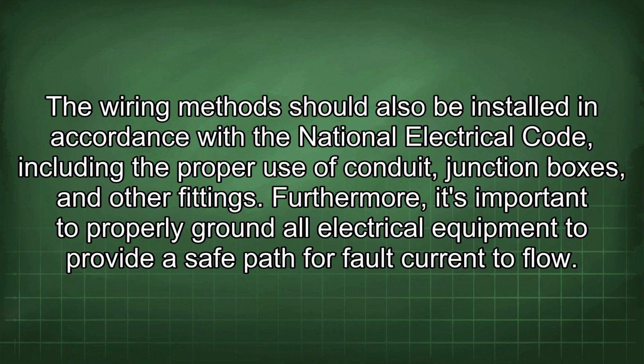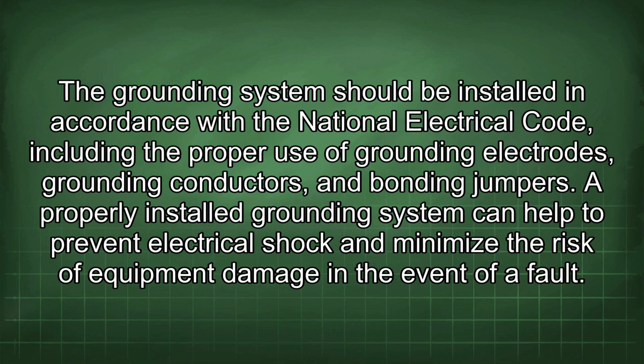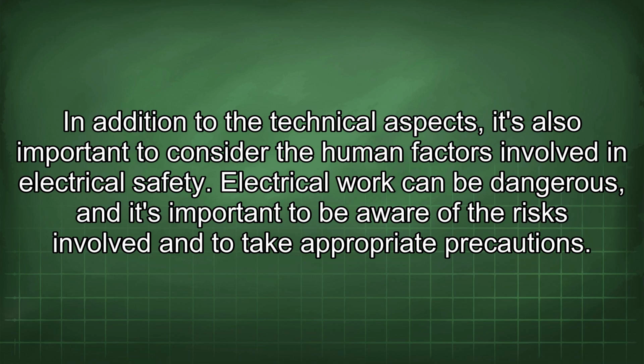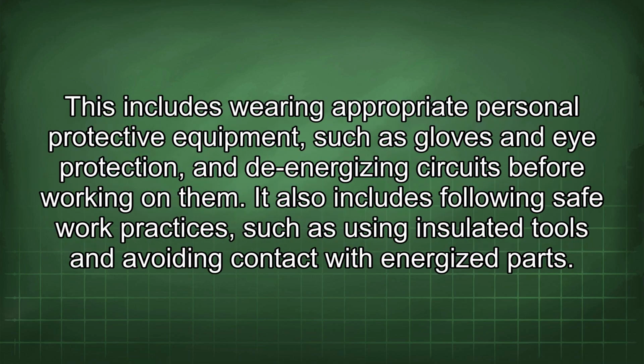Furthermore, it's important to properly ground all electrical equipment to provide a safe path for fault current to flow. The grounding system should be installed in accordance with the National Electrical Code, including the proper use of grounding electrodes, grounding conductors, and bonding jumpers. A properly installed grounding system can help to prevent electrical shock and minimize the risk of equipment damage in the event of a fault. In addition to the technical aspects, it's also important to consider the human factors involved in electrical safety. Electrical work can be dangerous, and it's important to be aware of the risks involved and to take appropriate precautions. This includes wearing appropriate personal protective equipment such as gloves and eye protection, and de-energizing circuits before working on them. It also includes following safe work practices such as using insulated tools and avoiding contact with energized parts.